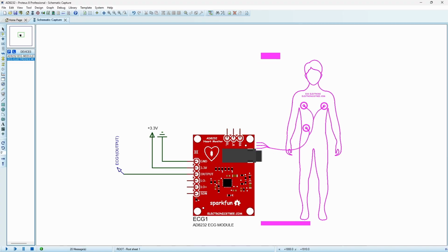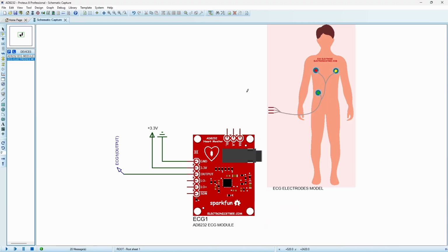The generator continuously reads the correction voltage and applies it in real time by subtracting it from both the RA and LA electrode signals. This accurately replicates how the human body behaves as a summing junction, where common mode noise and the inverted RLD signal combine. As a result, the AD8232 can effectively cancel common mode interference, giving you a much more realistic ECG simulation.